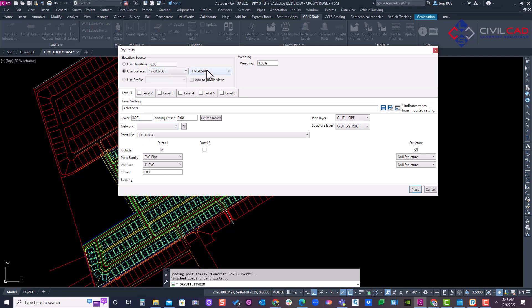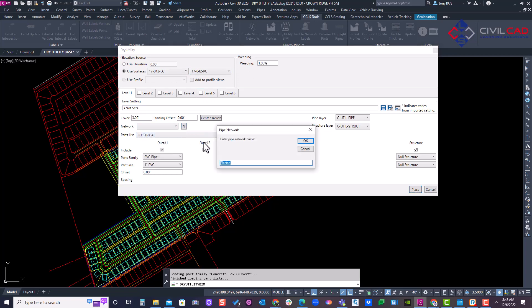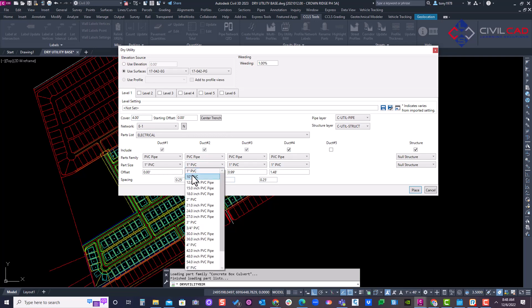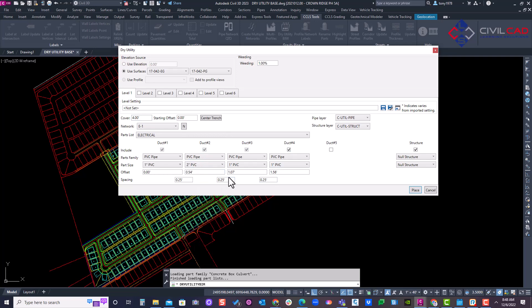It can follow a surface — I have existing and proposed, so if it can't find existing it'll look for proposed. It sees two surfaces in the drawing. I'll give it a name: E-1 for electrical network one. It's going to be four feet of cover. I'm putting four conduits — two-inch PVC in the center and one-inch PVC on the outer. You also have an option to offset off the polyline, left or right, using a negative value to go left.